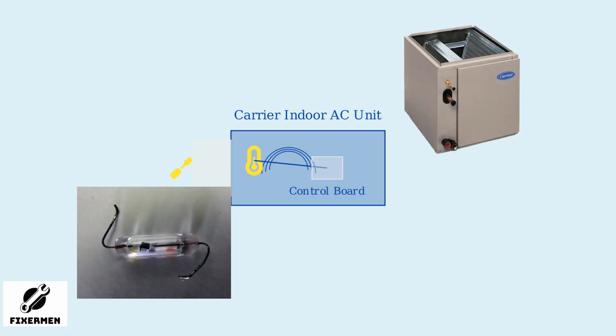The evaporator sensor in your carrier AC system is typically located on the evaporator coil inlet inside the indoor unit. This small thermistor monitors refrigerant temperatures and connects to the control board via wiring. To locate the sensor, you may need to remove the access panel, which often requires a screwdriver. Once inside, look for the evaporator coil and the small sensor attached to its inlet.